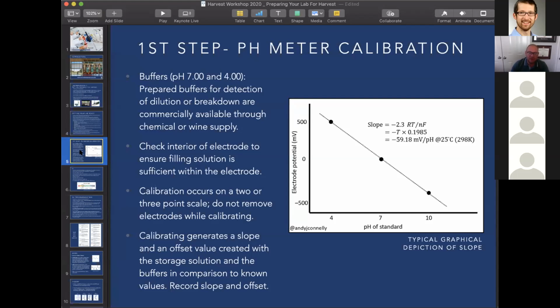That's very helpful because what the buffers do is create data points so that the pH probe can analyze the sample pH. If you're just doing the very basic, you can get nice 4 and 7 buffers, and replace them every 6 to 8 weeks. Make sure that you have enough. They can come from Carolina Wine Supply, that's fine. Ensure that those buffers are accurate. When you put your probe in, make sure that they are 4 and that they are 7. I've had problems getting buffers that were inconsistent. Maybe they were too high, maybe they were too low. So buffers are definitely a source of constant turmoil. Making sure that you have great buffers is part of doing the pH measurement. You just have to make sure that you work with those buffers correctly and that they're fresh.